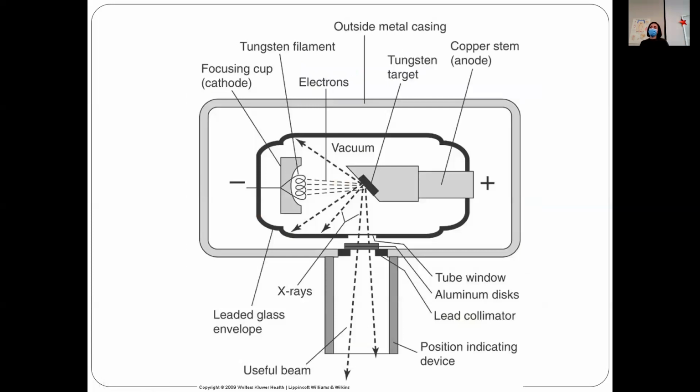All right, so here's a refresher of the whole system again. This is actually not to scale, because we know the vacuum glass tube is much smaller, since you've all now seen the X-ray tube in the room. It's like this big, and the tube is only like this big. You have the vacuum sealed leaded glass tube on the very inside with the anode and the cathode. Then you have the larger metal tube head encasing it, filled with insulating oil all around it.